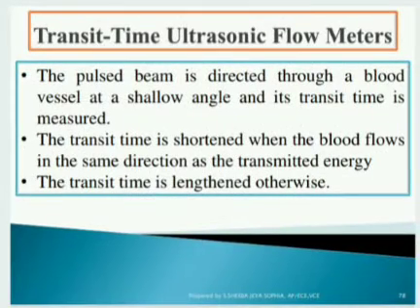As the name suggests, ultrasonic flow metering works based on the sound velocity. In transit time blood flow meters, the pulsed beam is directed through the blood vessel at a shallow angle and its transit time is measured.